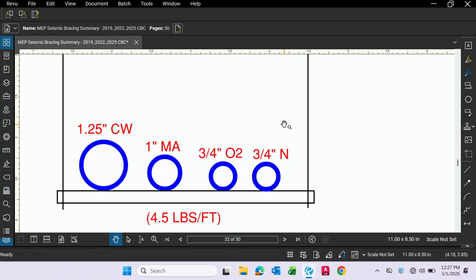But remember, there was a... did I forget the trapeze? I think we talked about that. Okay, sorry. If pipes are on a trapeze, the brace exemption is 5 pounds or less. So 5 pounds per linear foot. If the trapeze is 5 pounds per linear foot or less, it can be exempted, but you still have to keep the size exemption. So this one, the whole trapeze weight is 4.5 pounds, so the requirement for trapeze bracing is not met. This whole thing doesn't need to be braced.